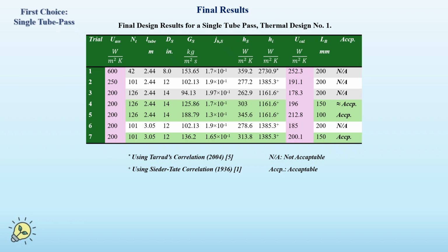As shown in this table, we have the first estimation for a tube length of 2.44. We have used 5 iterations. Of course, even the baffle spacing was altered to arrive at acceptable percentage deviation between the assumed and calculated values.